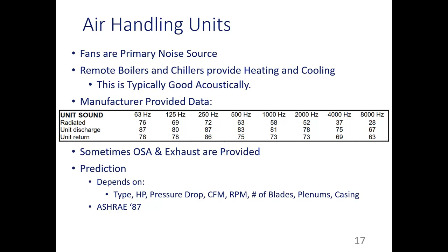Oh, so you get that bare fan sound power level. And if you don't know any better, you need to assume half of that goes to the supply and half goes to the return. At this point, if we were in class, I would ask you how you account for that. Maybe you want to pause this and think about it for a minute. So you're back. We have the bare fan sound power level. Half of it's going one direction, half the other direction. So we would just take that bare fan sound power level and subtract 3 from all the octave bands, right?